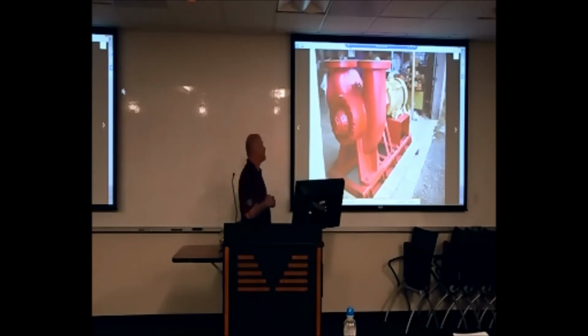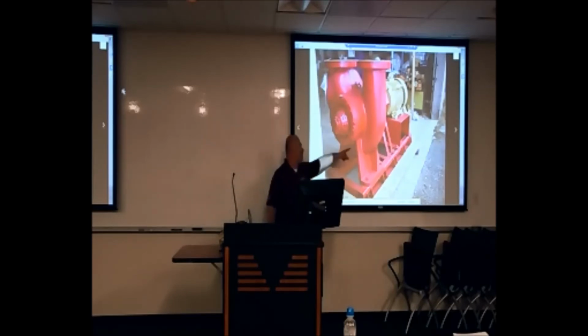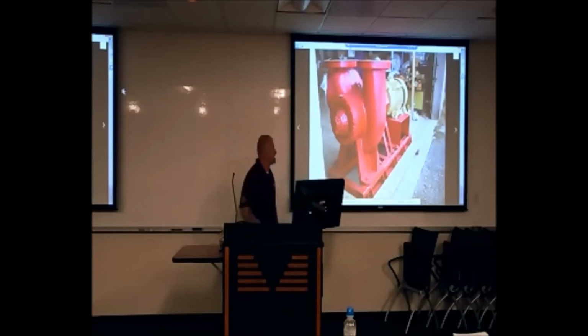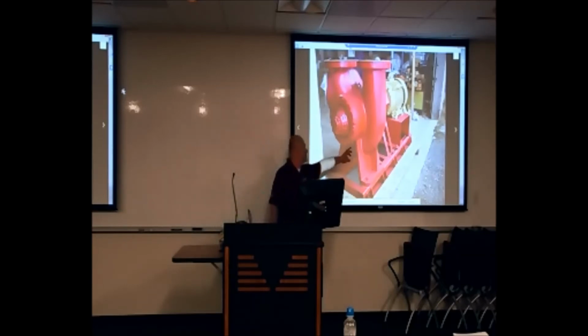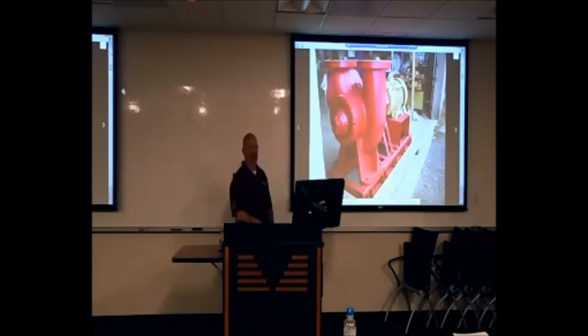And of course, whenever you're doing service, we do put a drain plug on the bottom. Some people often miss that, and they'll go and isolate the pump and then go pull the side bits off, and huge amounts of water come out of there. So make sure that you do drain your pump, and you don't want to get all wet when you're doing your servicing. I always forget that, even myself. Sometimes I've walked up, isolated the pump, 'Oh, let's just pull it off here.' Pant legs covered in water. So keep that in mind. You always want to drain that pump out.